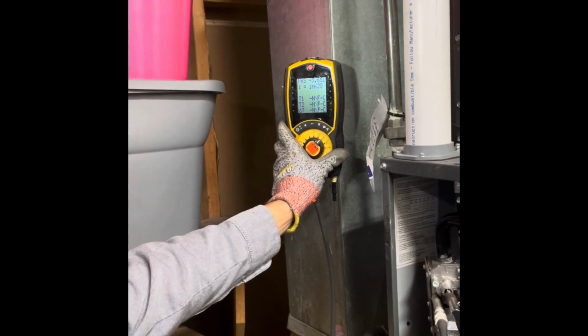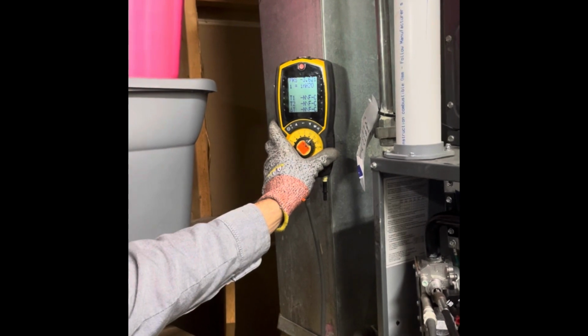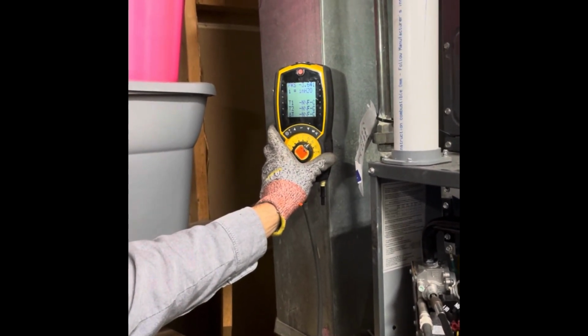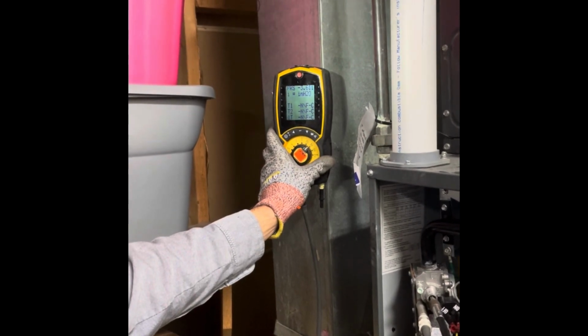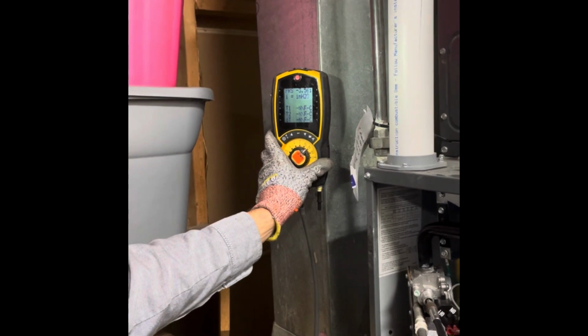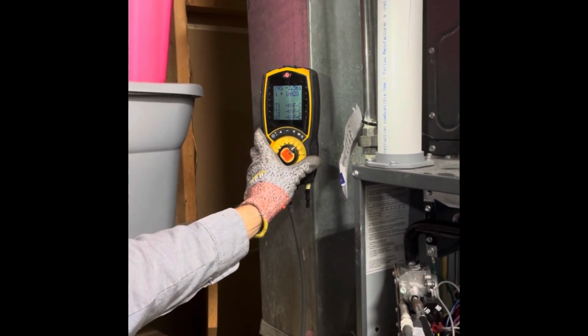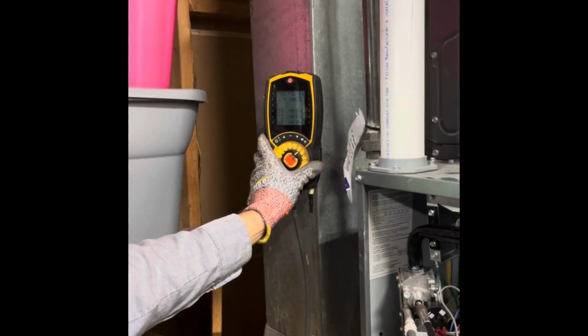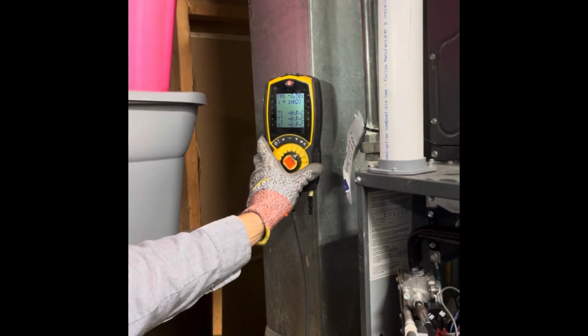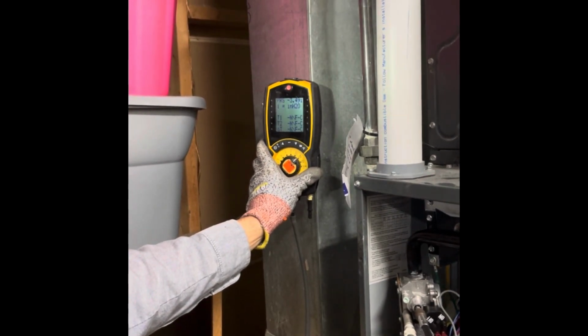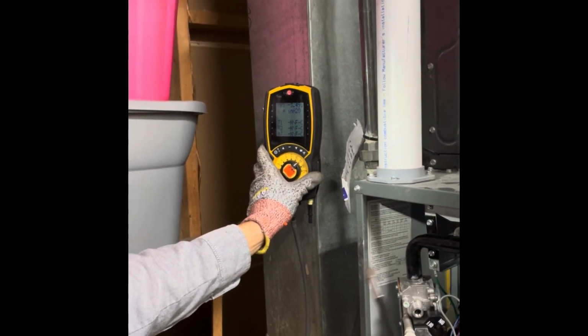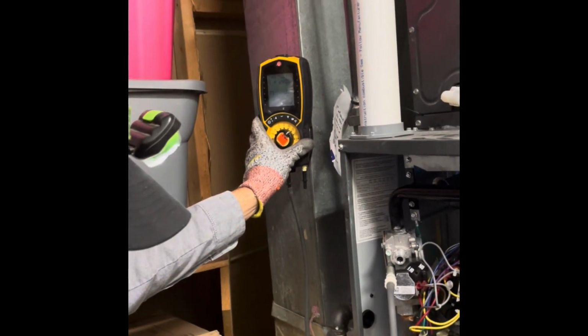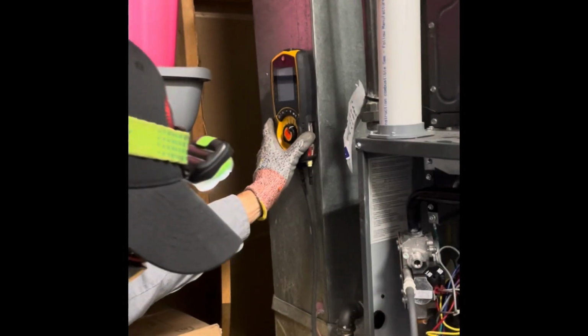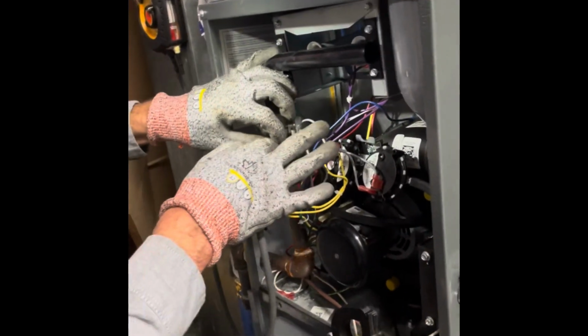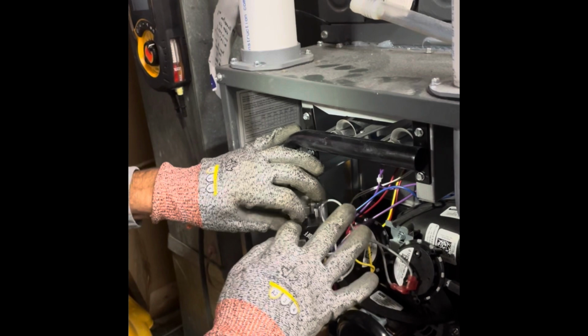And why it's important to have the gas pressure set properly: if my gas pressure is too low, I'm not going to get good heat in the home. And if it's too high, it's going to create too much heat, which could cause our furnace to do what they call a short cycle. So when that happens, the furnace overheats, our burners turn off, it goes off on a high limit safety, and then our blower runs for about 5, sometimes 10 minutes trying to cool down that metal before it'll start back up. If your furnace is short cycling, it's going to repeat this process day and night. And at the end of the month, when you get your hydro bill, expect to see a very high cost, because the house isn't heating well and the furnace isn't working properly due to it overheating.